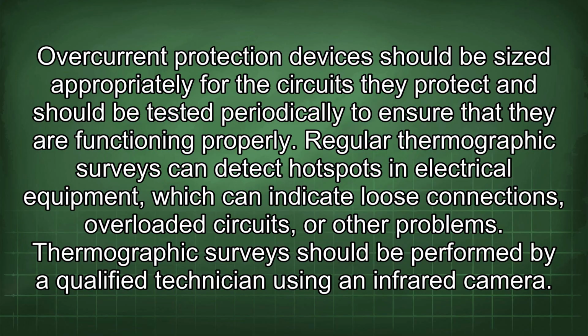Regular thermographic surveys can detect hotspots in electrical equipment, which can indicate loose connections, overloaded circuits, or other problems. Thermographic surveys should be performed by a qualified technician using an infrared camera.